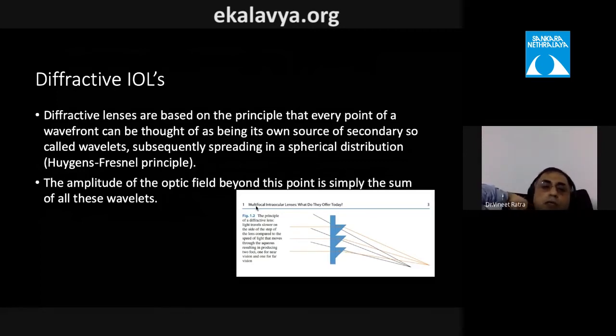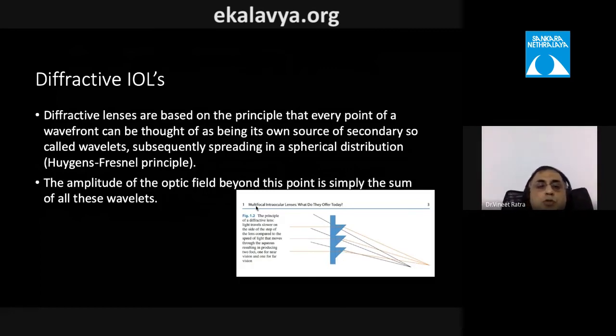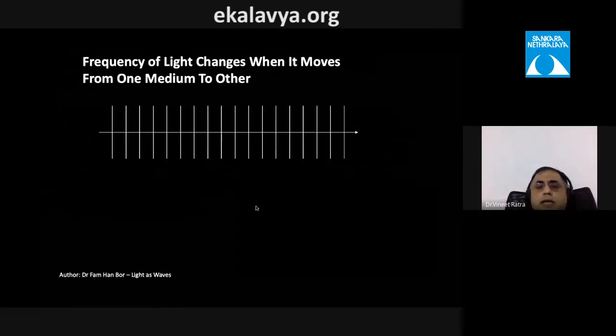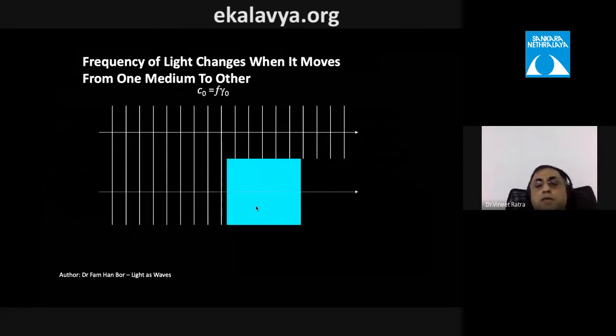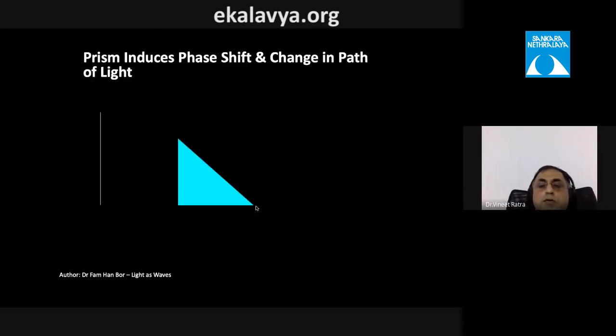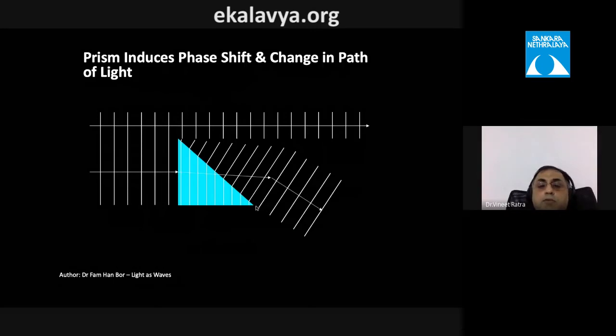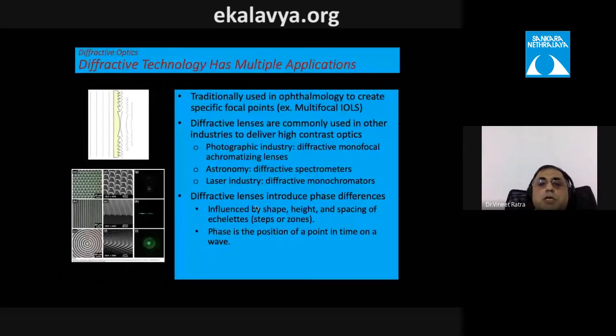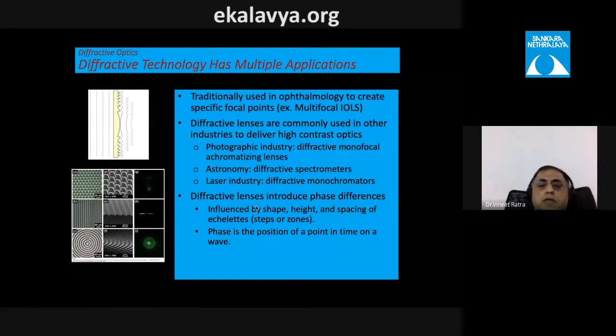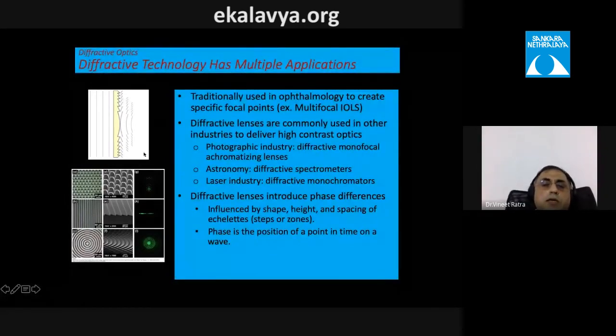Diffractive IOLs are based on Huygens-Fresnel principles, in which every point of a wavefront acts as a secondary source of wavelets. The sum of these wavelets creates the optical field. Diffraction combined with the change in speed of light through the lens medium bends rays to focus at specific points. This technology — also used in photography, astronomy, and laser industries — produces designs with varying step height, width, and spacing.